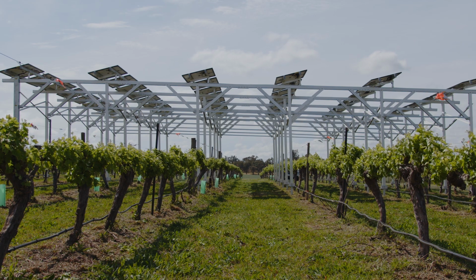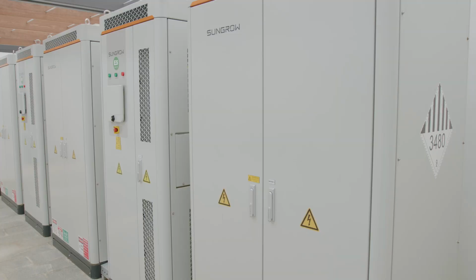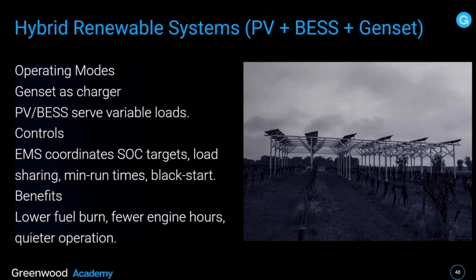Hybrid renewable energy systems: PV, BESS and genset. We have to take into consideration the operating modes, the genset as a charger, the PV and BESS to serve variable loads. There are all these controls: EMS coordinates state of charge targets, load sharing, minimum run times, black start. Now the benefits: lower fuel burn, fewer engine hours and quieter operation.